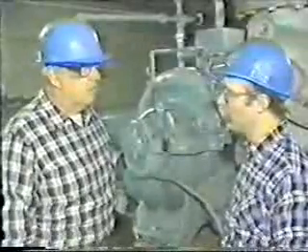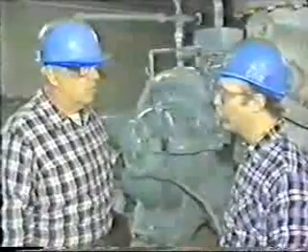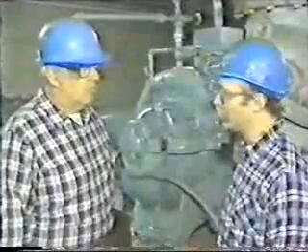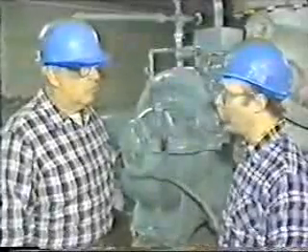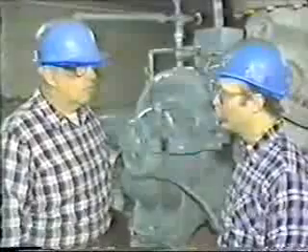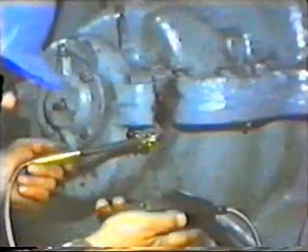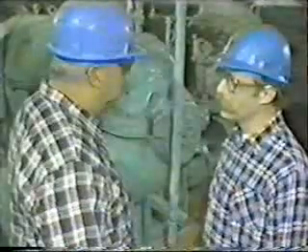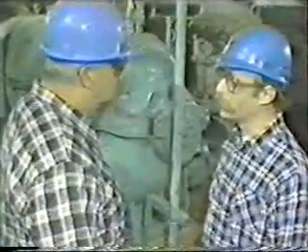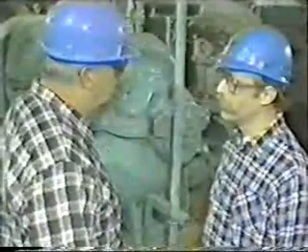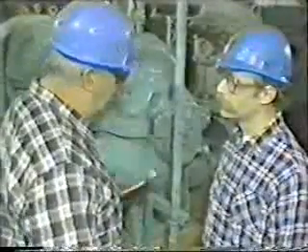The operator says that the temperature on the outboard pump bearing is up a little, not enough to cause him to shut down the pump, but enough to indicate a potential problem. The operator has been monitoring the temperature, but so far there's been no indication that it's still going up. The operator first noticed the temperature increase when he made his last rounds, about 30 minutes ago.